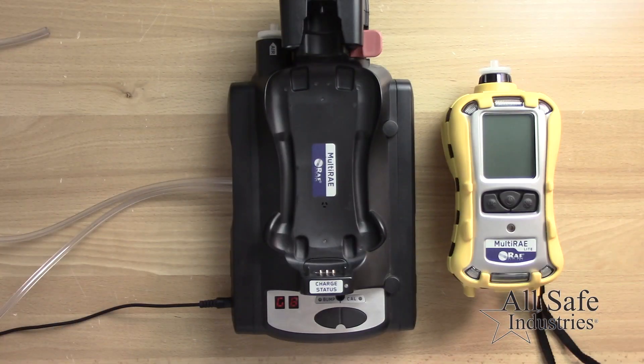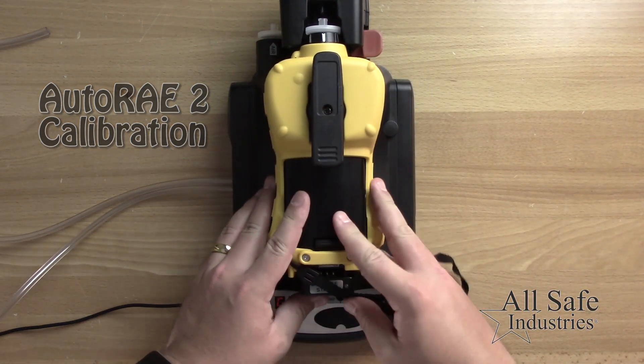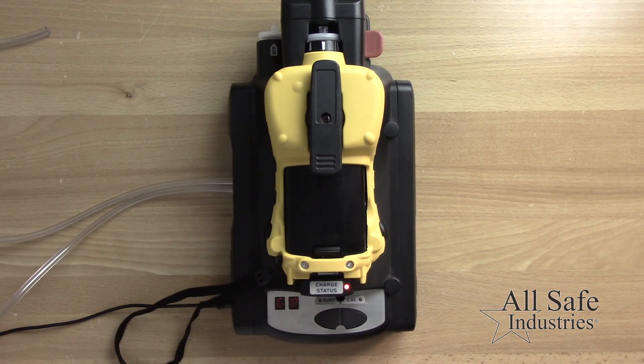To calibrate using an AutoRAE 2 calibration cradle, start with the MultiRAE turned off. Place the meter face down on the cradle and close the capture mechanism. You'll hear the meter turn on and begin the warm-up sequence.